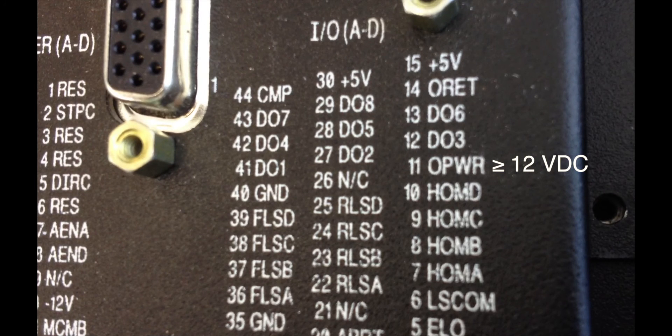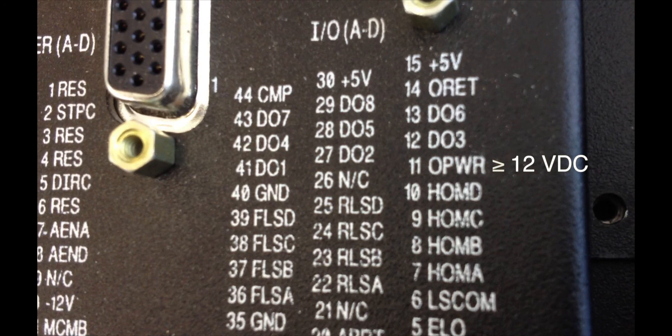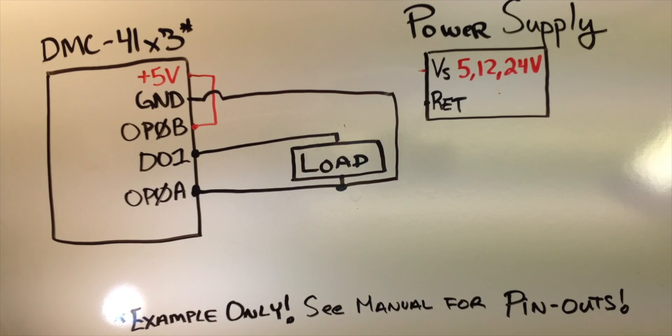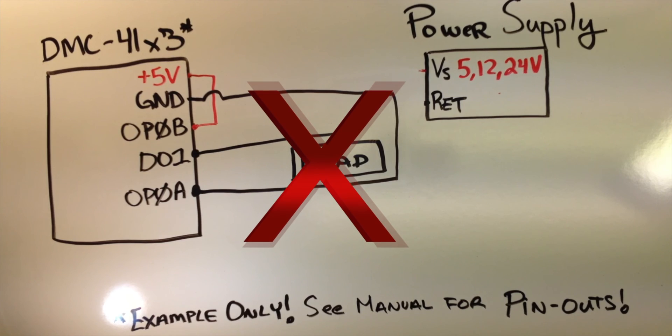Another important distinction is that the high sourcing option has a minimum supply voltage of plus 12 volts, so it cannot be powered using the plus 5 volt reference of the controller.